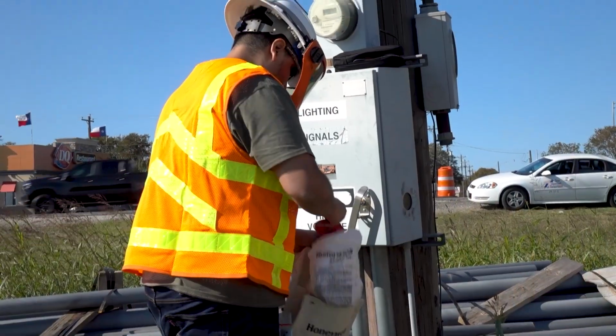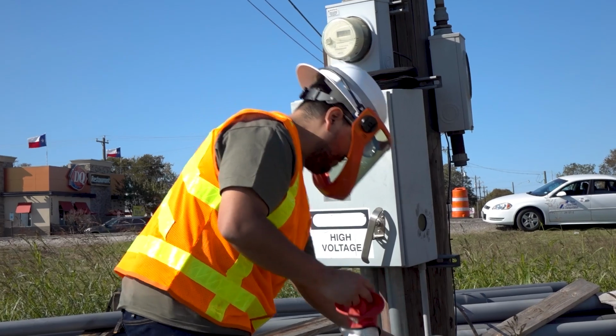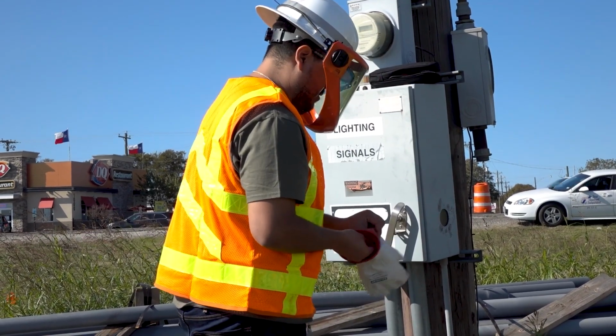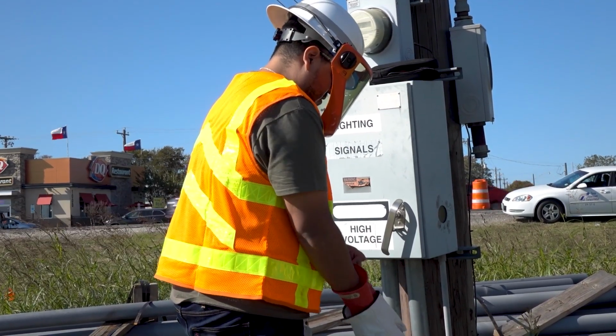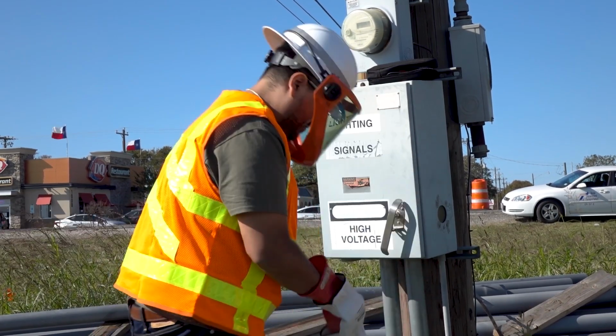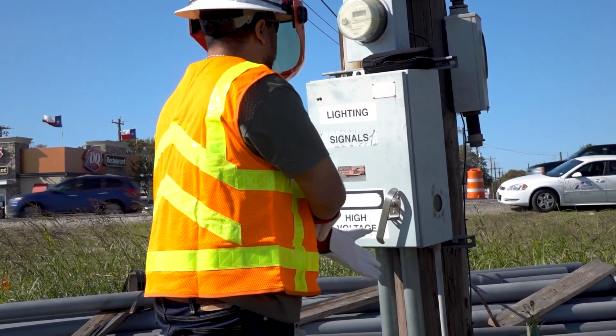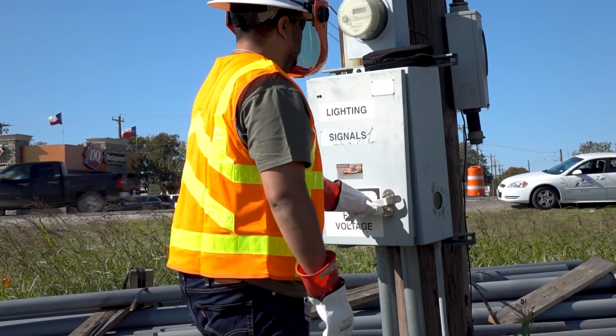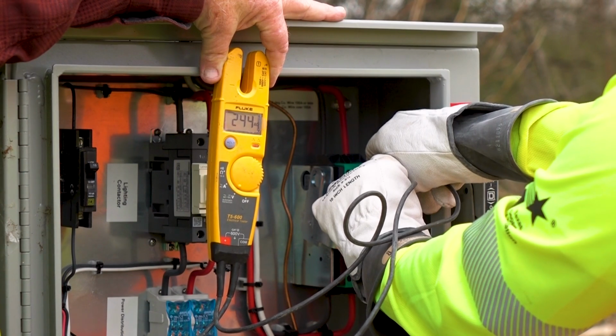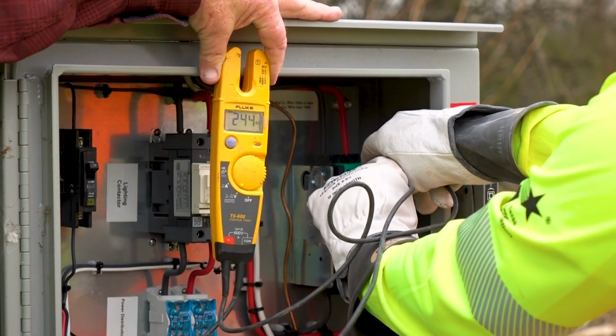The two conductors should not be touched unless the inspector is wearing the proper insulated gloves and personal protective equipment. While the conductors may appear safe and well insulated, they may have damage that is hidden from view. Metal parts of the top lugs of the breaker are exposed and are also a potential safety hazard.